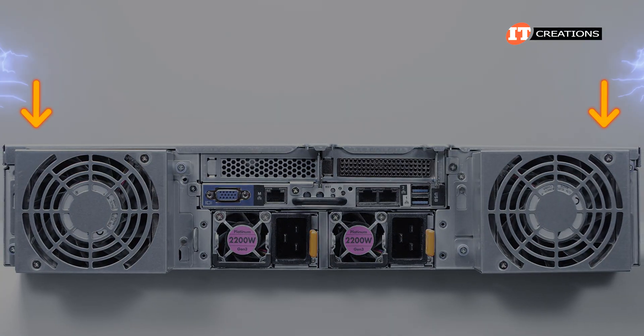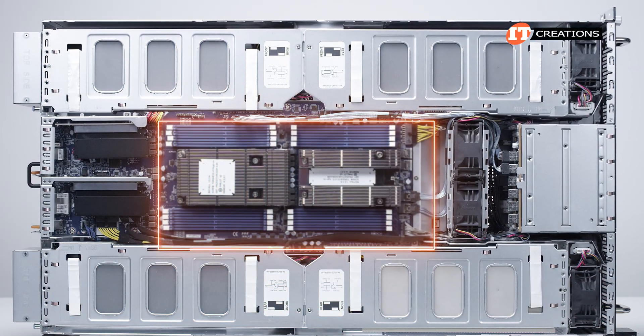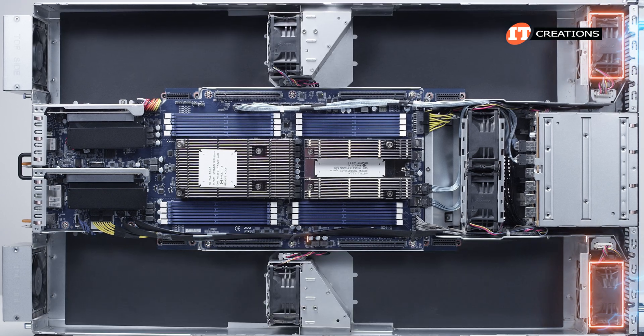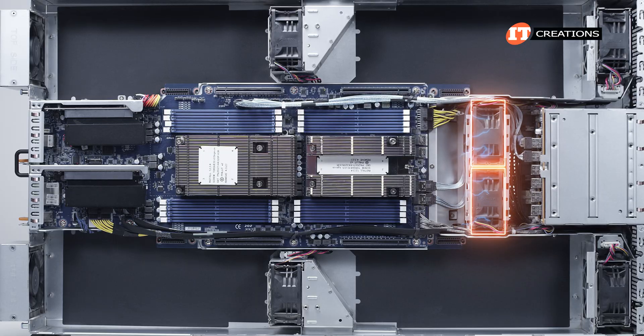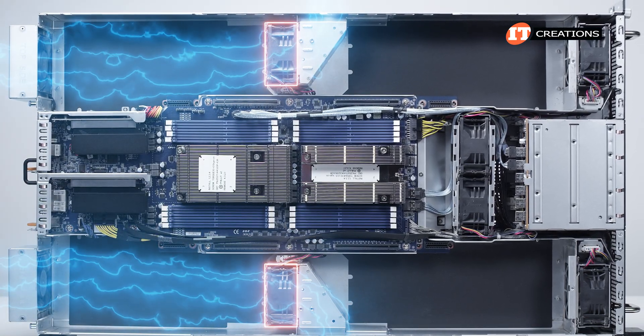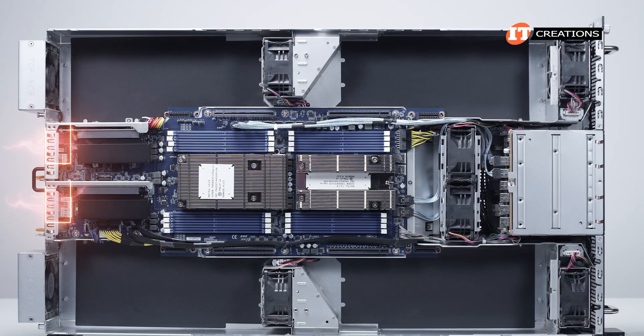There are vents about halfway down the sides of the chassis for pulling in fresh air. Once the cover panel is removed, you can see a very compact layout with several fans and a plastic cowl over the CPU and memory module slots. There are three clear thermal zones. For the eight GPUs, there are two GPU cages stacked on each side for four GPU riser cages total, each housing two GPUs. Front fans blow cool air into the chassis for the first set of GPU risers, directed mostly under the slightly raised motherboard, while fresh air from center front fans pushes over the motherboard, GPUs, memory modules, and PSUs mounted underneath. For rear GPU risers, a large fan behind the side vent pulls fresh air through perforated panels, and two rear fans exhaust that air out the back. PSU integrated fans also help pull heated air out.